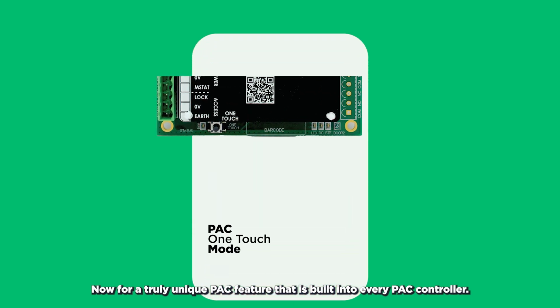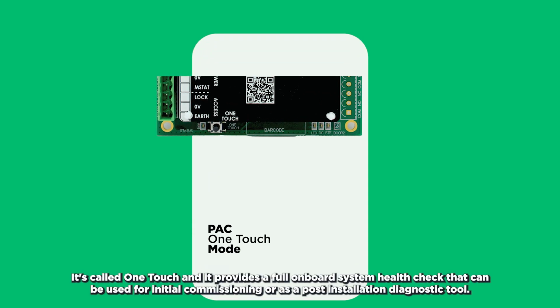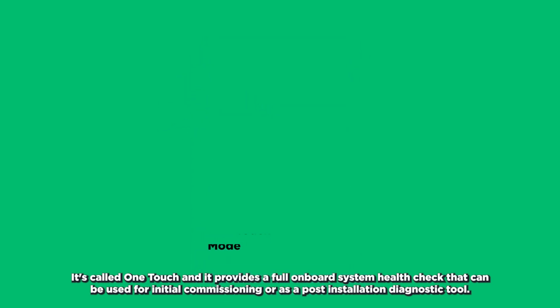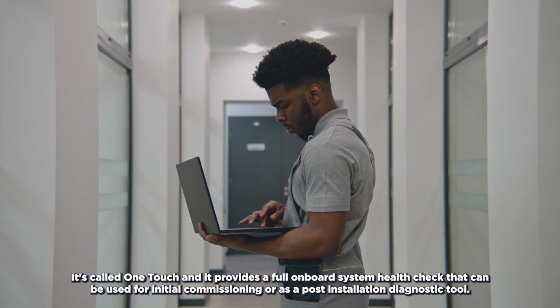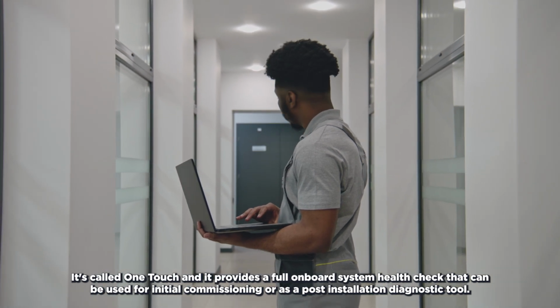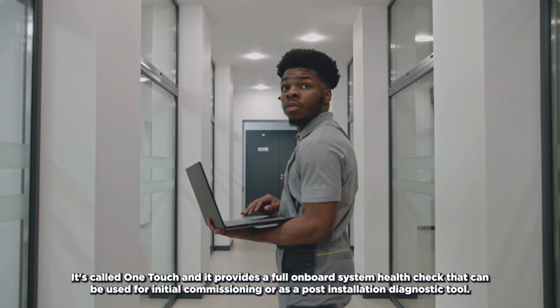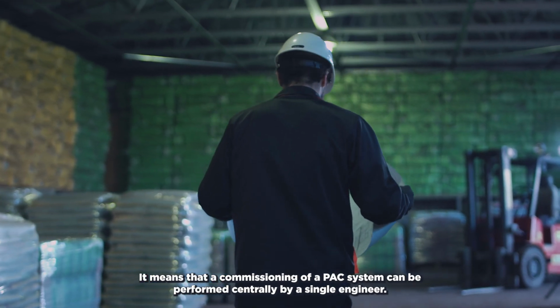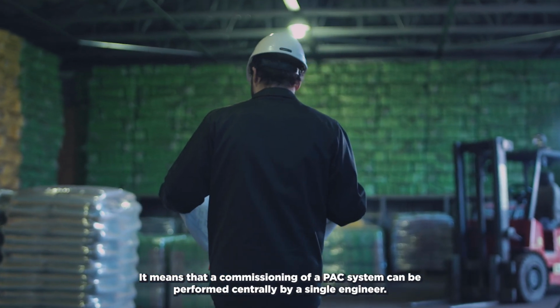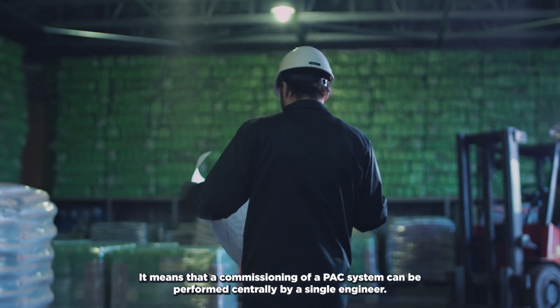Now for a truly unique PAC feature that is built into every PAC controller. It's called One Touch and it provides a full onboard system health check that can be used for initial commissioning or as a post-installation diagnostic tool. It means that a commissioning of a PAC system can be performed centrally by a single engineer.